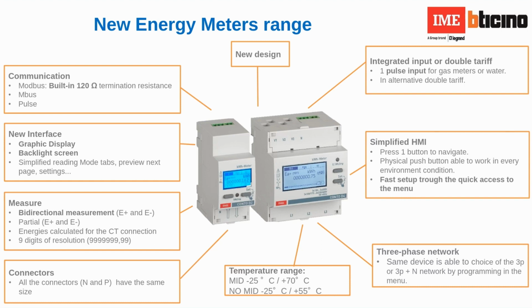There is the possibility to receive and store pulse from a third-party gas or water meter, and view this consumption of gas or water on the display, or also remotely via Modbus. In alternative, the inputs can be used also for tariff change, as we have embedded also double tariff input. As you can see in the bottom part of this slide, a very important feature for several applications, for example, like electrical vehicle charging station, is the operating temperature up to 70 degrees Celsius, this for the MID version. The MID certification is mandatory in Europe to re-invoice the energy.